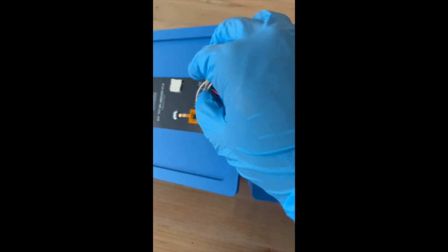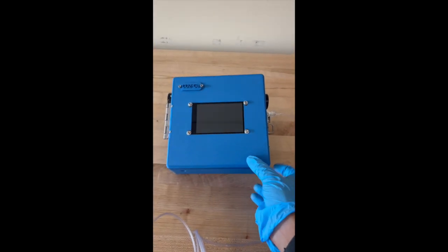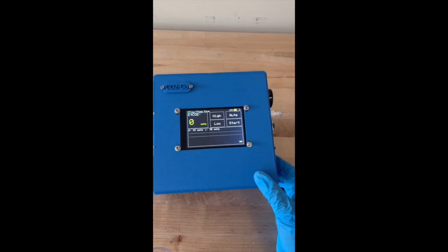And this wire that I just ran my hands through goes to the screen and enables us to display the capnographic waveforms, all the alarms, and have touchscreen enabled for the users to be able to use. If you switch the device back on by just simply pressing the switch and closing the toggle latch, it's good as new and ready to keep going.